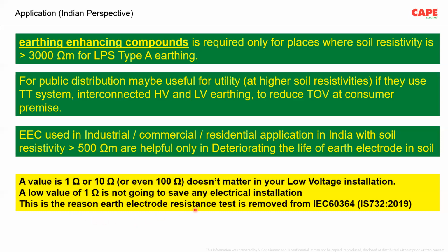This is the reason earth electrode resistance test is removed from the IS732. All of us know very well that whenever there is an electrical safety audit, the first thing we do is the earth pit resistance measurement. Actually, in the IS732 2019, this has been removed. You don't need to test it anymore for the purpose of electrical safety because it is not going to help you.